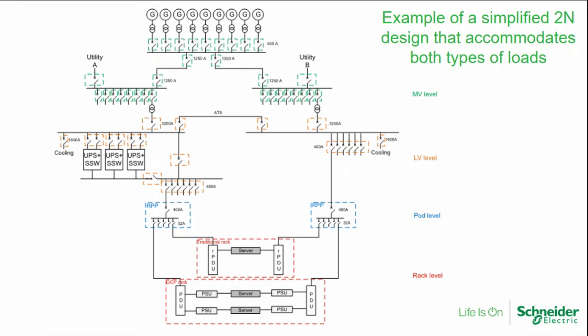Right-sizing all the components, only putting what's necessary — getting rid of extras like load bank connections. This is a 2N design, the most typical architecture for enterprise data centers and co-location, but the UPS system is only on one side. You still have two paths and can do concurrent maintainability, with battery backup on one side, which optimizes cost and increases efficiency. At the bottom we're demonstrating how you can have traditional servers fed off regular circuits, and off the same RPP you can have open compute racks.